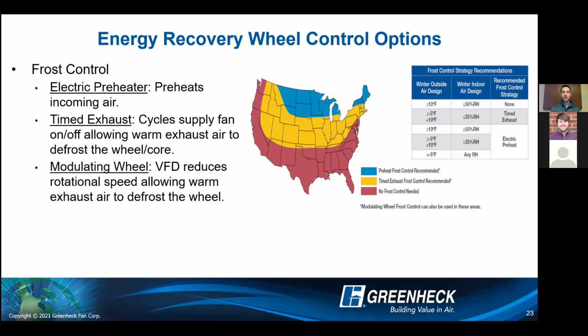And then a modulating wheel uses a VFD that reduces the rotational speed so it spends more time in that return airstream, again to melt those frost conditions. The biggest thing to know in relation to frost control is it really does depend on both your application and where you're located. So as you can see in the Georgia market, generally no frost control really is needed because you don't get cold enough where there's going to be a concern.